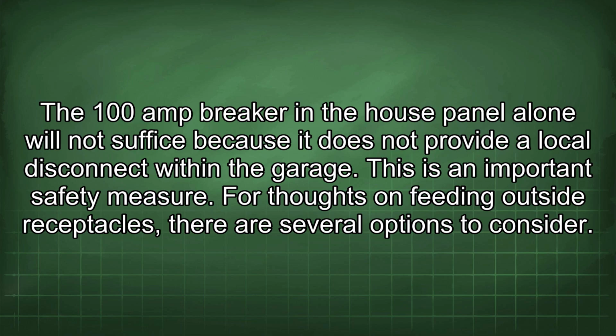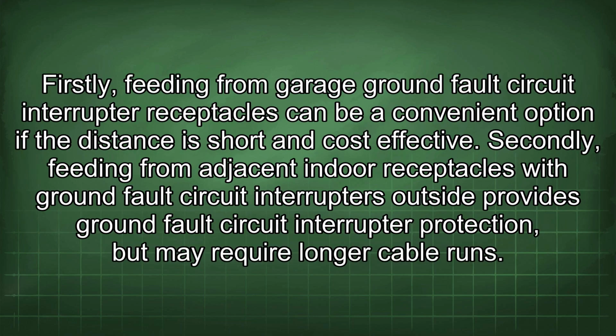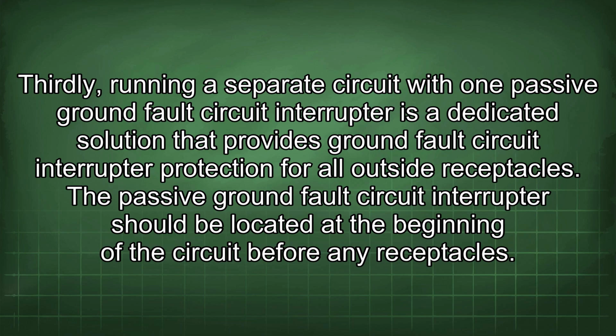For thoughts on feeding outside receptacles, there are several options to consider. Firstly, feeding from garage ground fault circuit interrupter receptacles can be a convenient option if the distance is short and cost-effective. Secondly, feeding from adjacent indoor receptacles with ground fault circuit interrupters outside provides ground fault circuit interrupter protection but may require longer cable runs. Thirdly, running a separate circuit with one passive ground fault circuit interrupter is a dedicated solution that provides ground fault circuit interrupter protection for all outside receptacles. The passive ground fault circuit interrupter should be located at the beginning of the circuit before any receptacles.